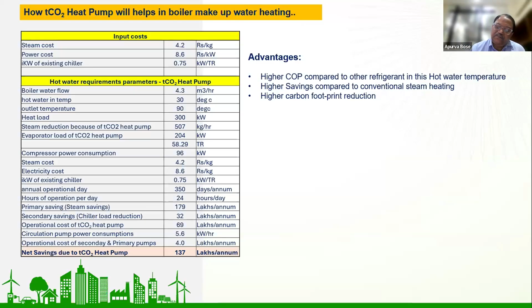So this is something which makes a prominent case for why we should be using a TCO2 based heat pump. However, one more thing I want to add here: a TCO2 heat pump makes sense only in those applications where the delta temperature is higher. Like you want to heat from 25, 27 degrees Celsius to 90 degrees or above, and you want to have the cooling solution also. So these are the places where it makes sense.